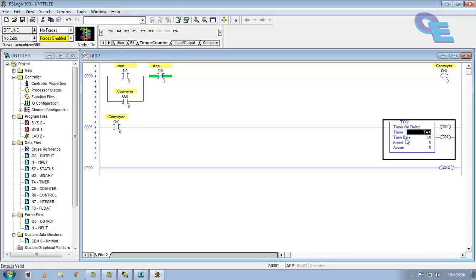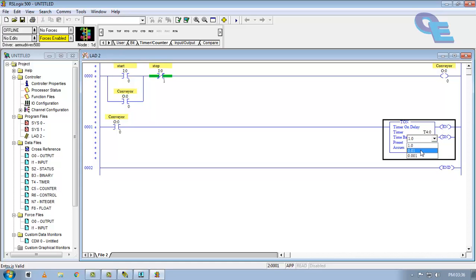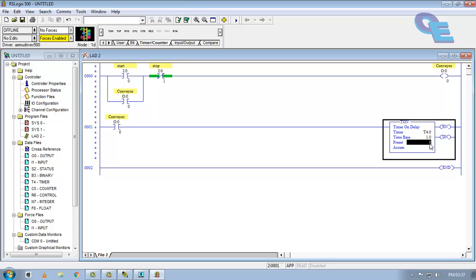Now time base is also important. Multiply the time which you are going to specify with this time base value, you are getting the time constant value. If I take 0.01, I have to specify the preset value as 500. In preset value I am going to set as 5 seconds. Accumulator value shows the current time here.